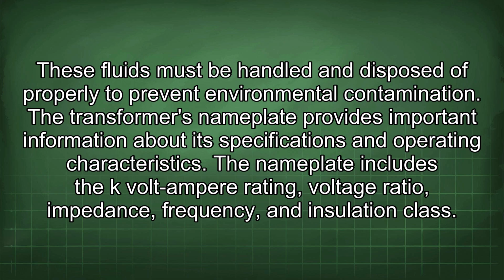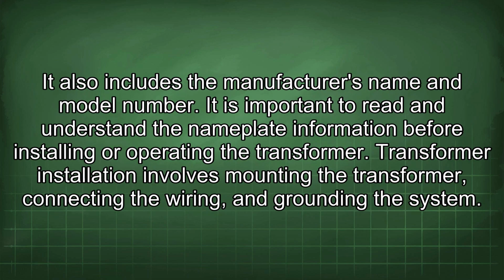The transformer's nameplate provides important information about its specifications and operating characteristics. The nameplate includes the kVA rating, voltage ratio, impedance, frequency, and insulation class. It also includes the manufacturer's name and model number. It is important to read and understand the nameplate information before installing or operating the transformer.